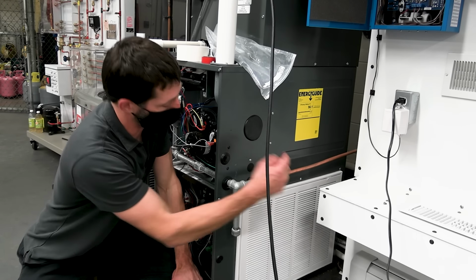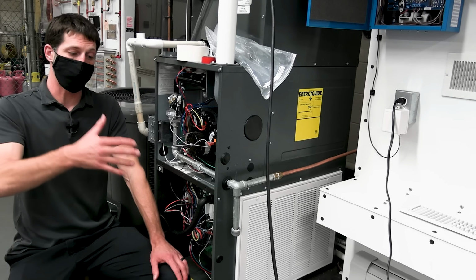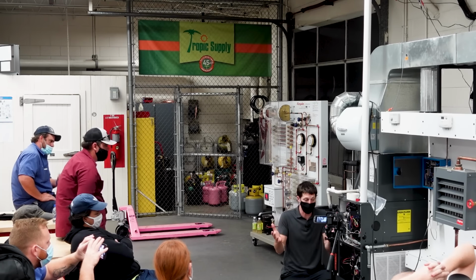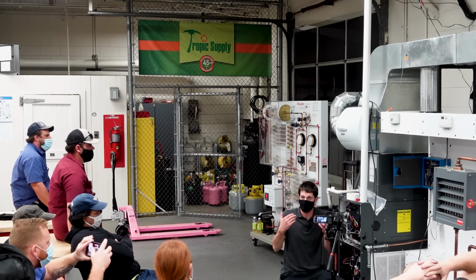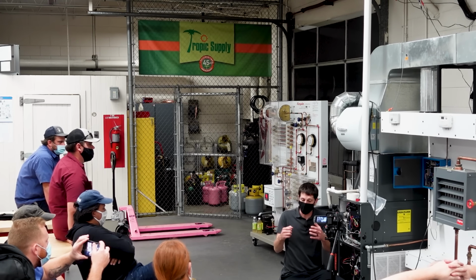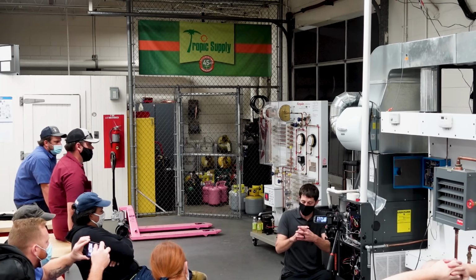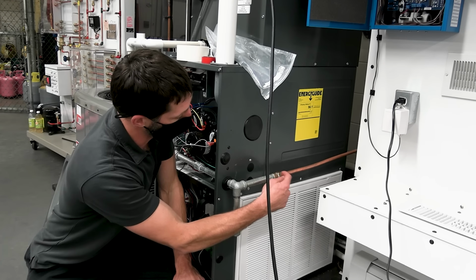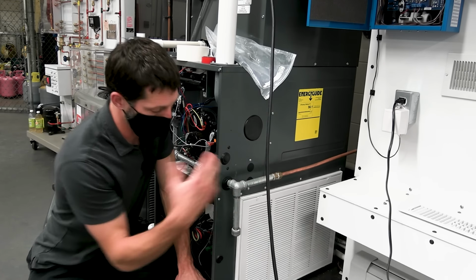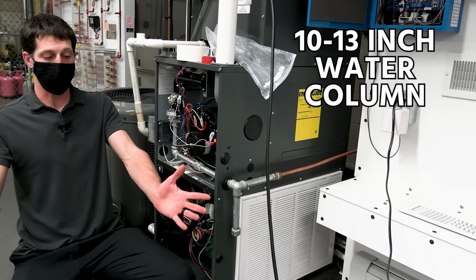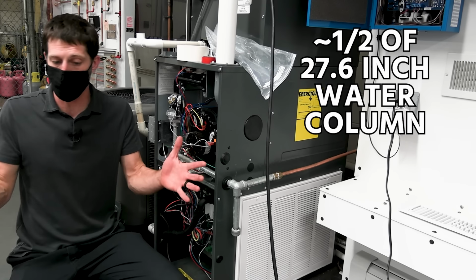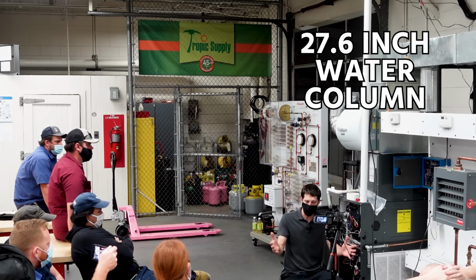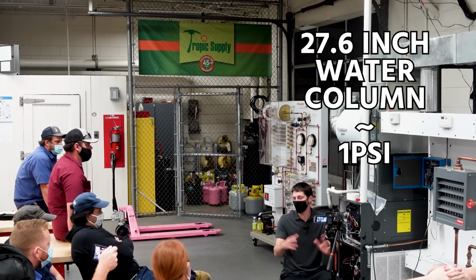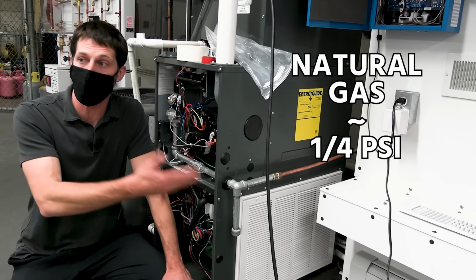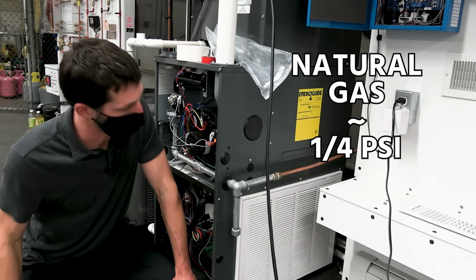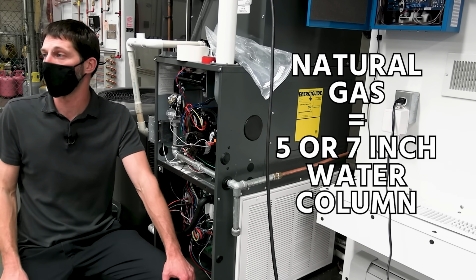But on a gas line, because it's a lower pressure than refrigerant, like an R410A mini split, we usually put, or at least I usually put, a refrigerant oil or Nylog on the flare face and then tighten that in. On a gas line, I typically don't put anything on that. Like I said, for propane, it's 10 to 13 inch water column, which is about half of 27.6 inch water column. 27.6 inch water column is about 1 PSI. All that to say, propane's about half a PSI, natural gas is about 1/4 of a PSI, because natural gas runs about 5 to 7 inch water column.